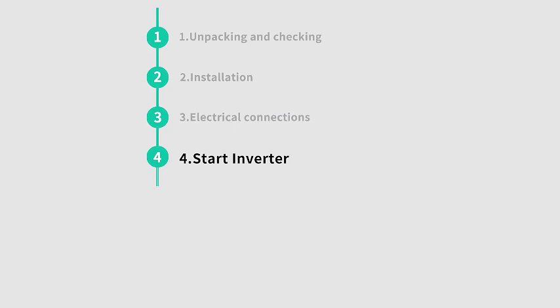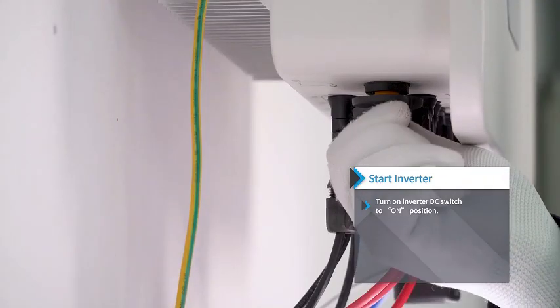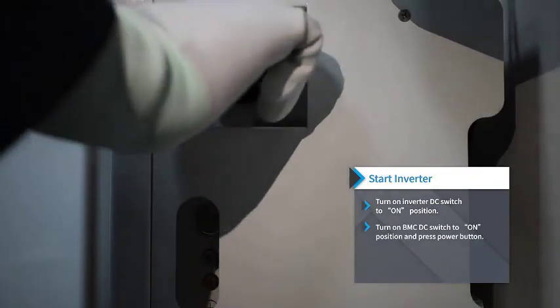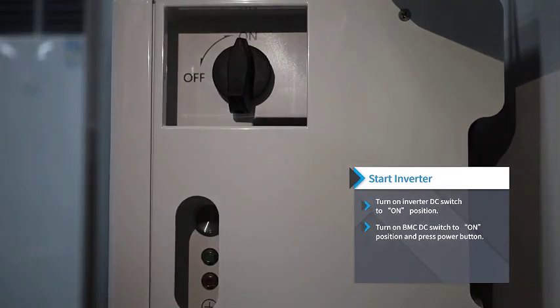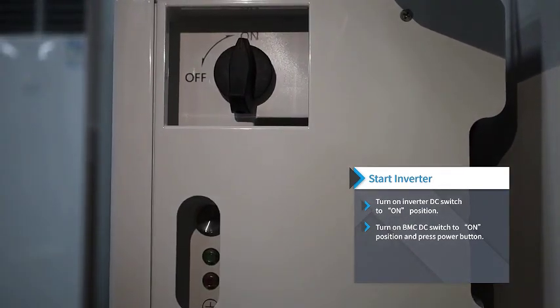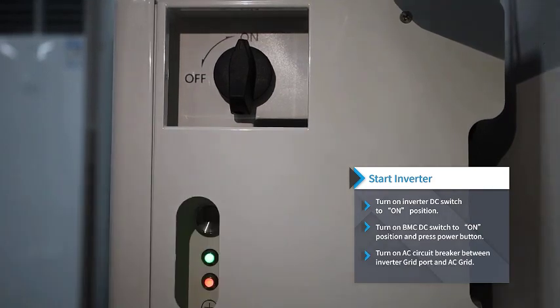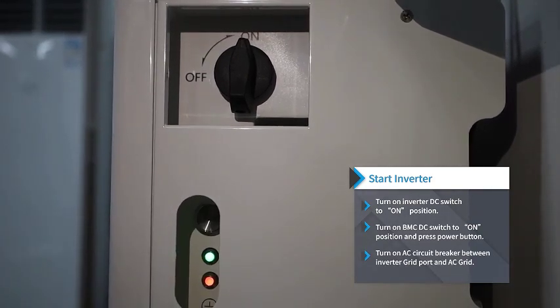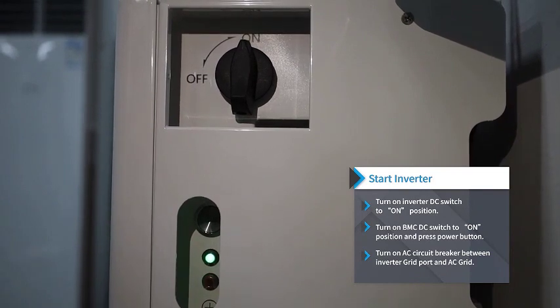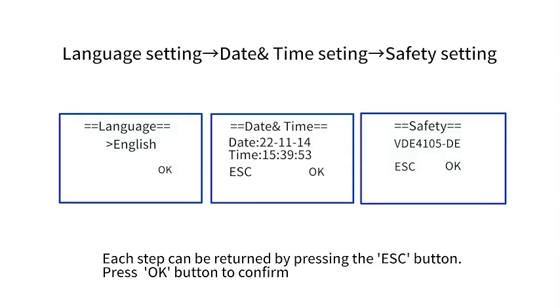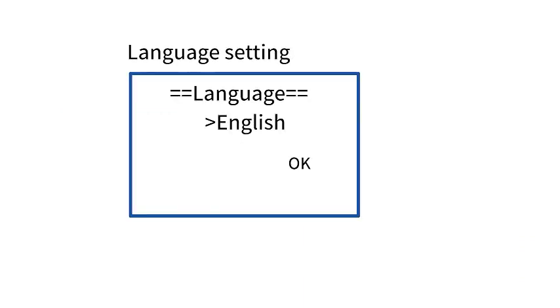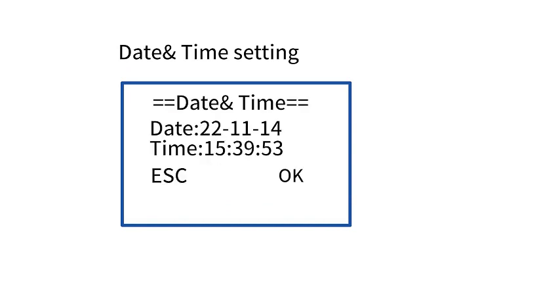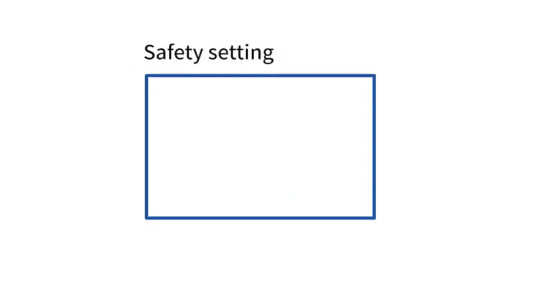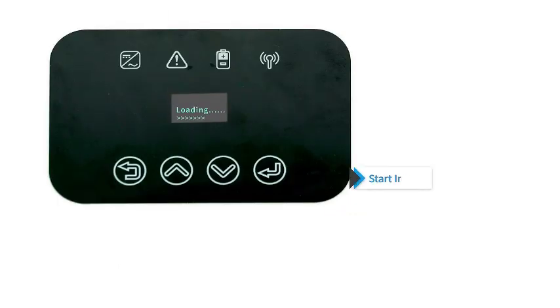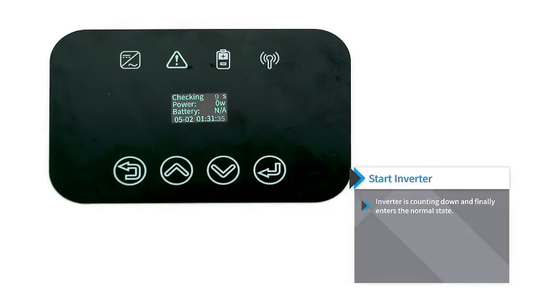Start inverter. Turn on the inverter DC switch to the on position. Turn on the BMC DC switch to the on position and press the power button. Turn on the AC circuit breaker between the inverter grid port and the AC grid. The inverter is counting down and finally enters the normal state.